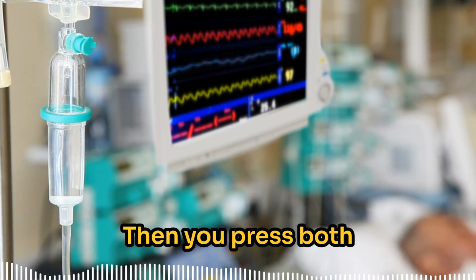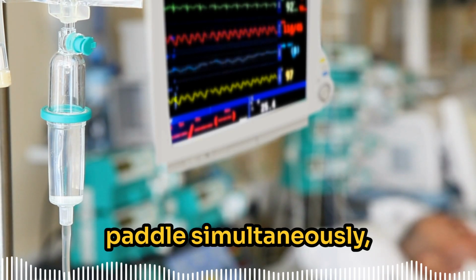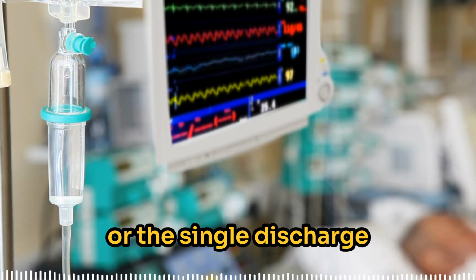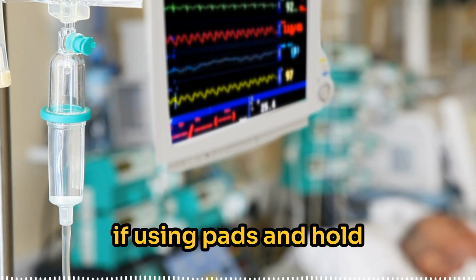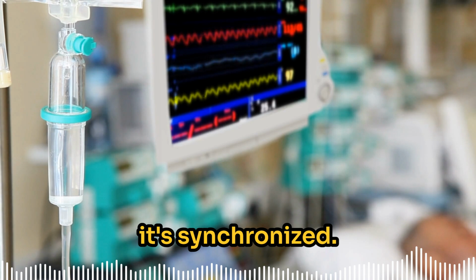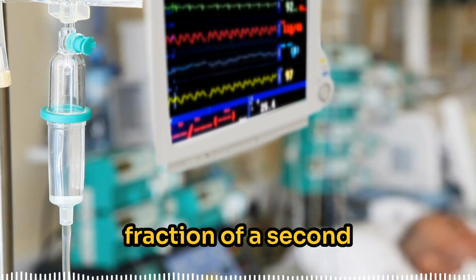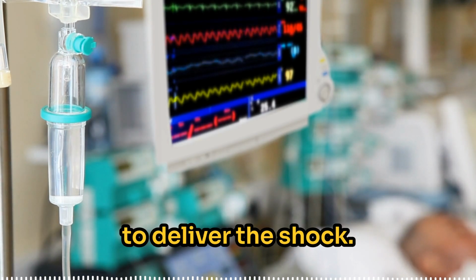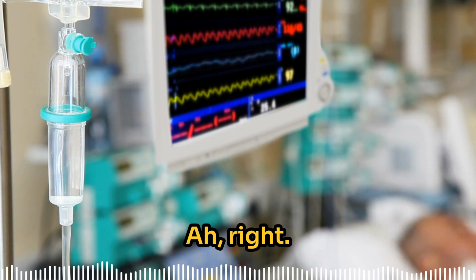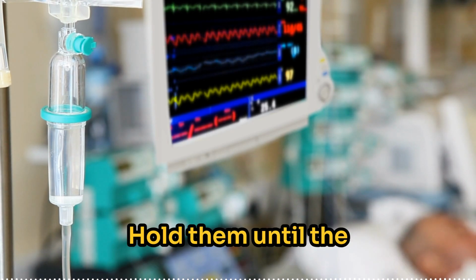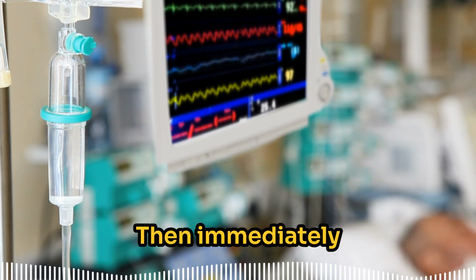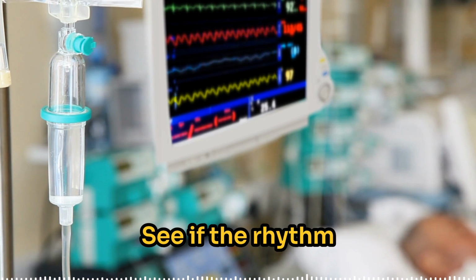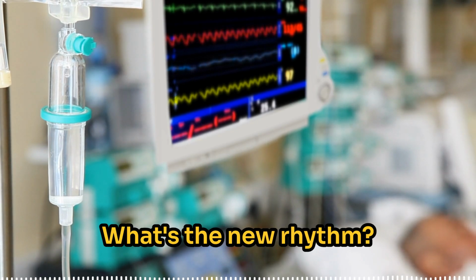Then shock. Then you press both discharge buttons on the paddle simultaneously, or the single discharge button on the machine if using pads, and hold them down. Because it's synchronized, remember, the machine might wait a fraction of a second to deliver the shock on the next R wave. Right. Don't let go too soon. Exactly. Hold them until the shock is delivered. Then immediately look at the patient and look at the monitor. See if the rhythm changed. Did it work? What's the new rhythm?